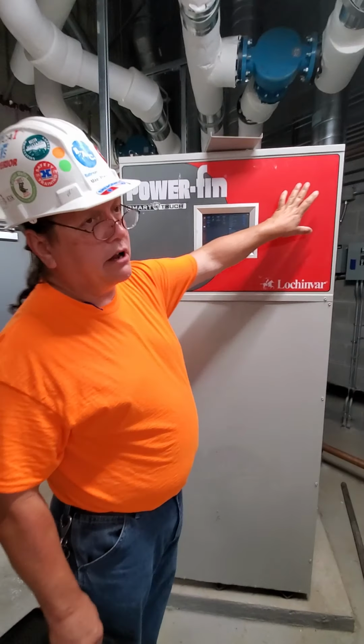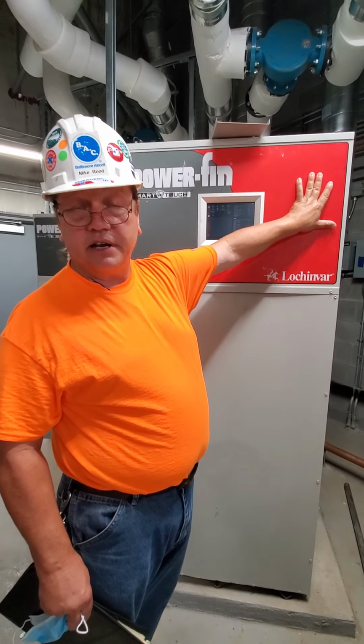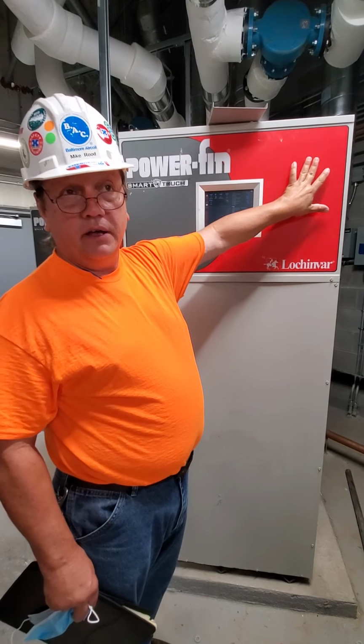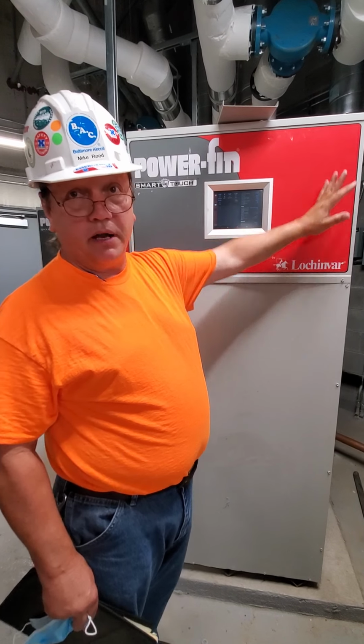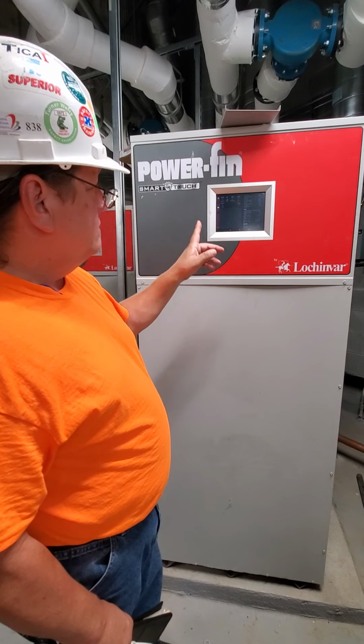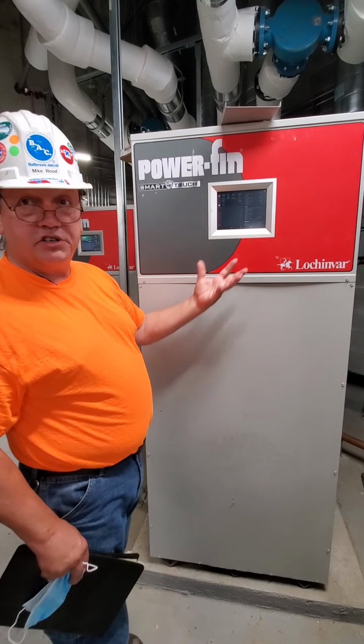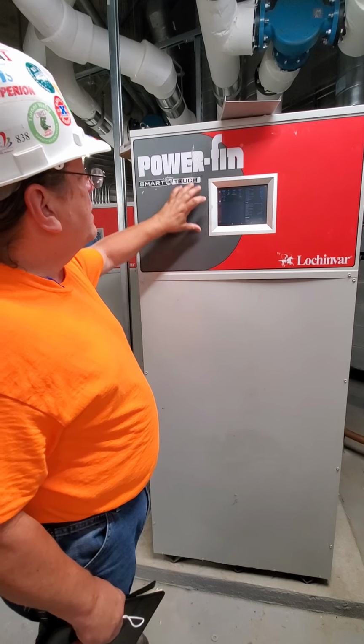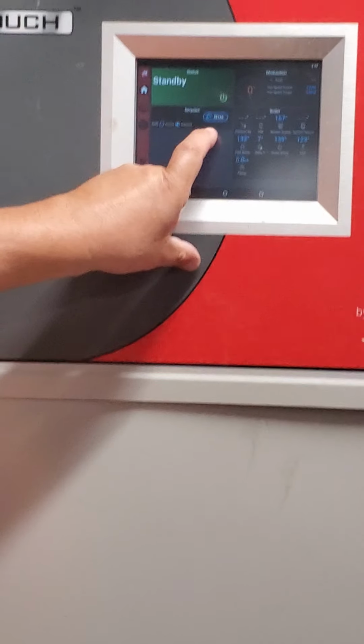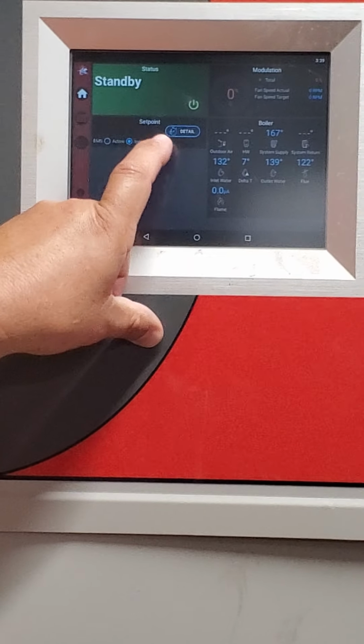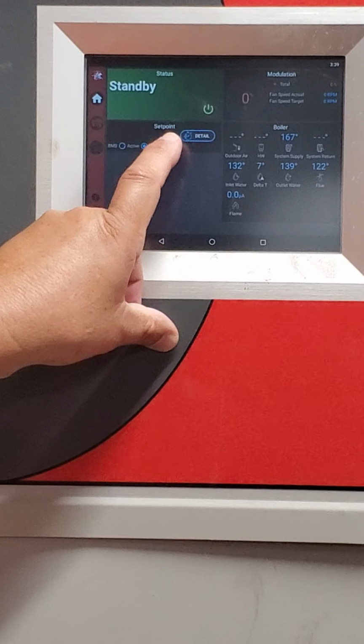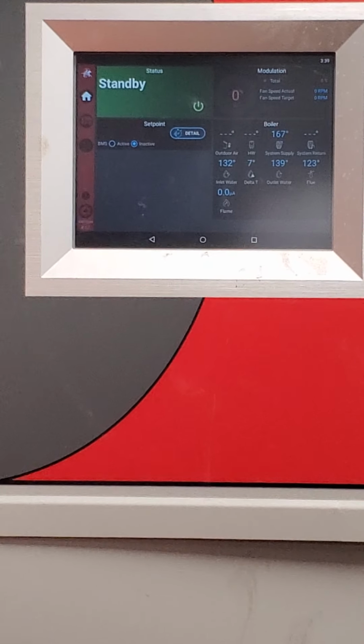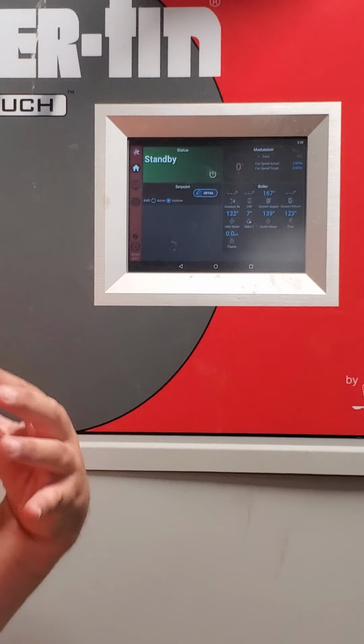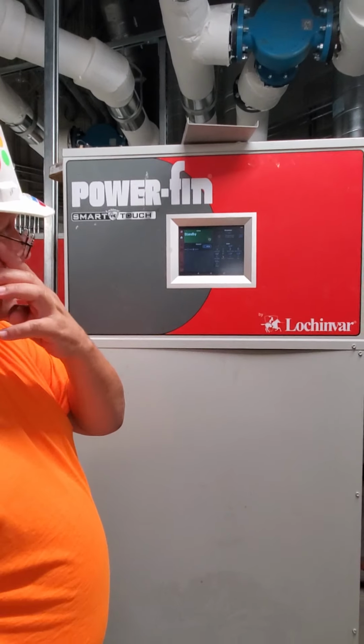There is a low water cutoff button in here for models that have a low water cutoff. There's a test button and a reset button. If it's locked out on flow switch or low water cutoff, you can press the reset button on the main screen, and that button will pop up if it's locked out. It will not show if it's not locked out. If you hit the reset button, the screen resets, and it sits there for about 15-20 seconds and does not reset and locks out again.